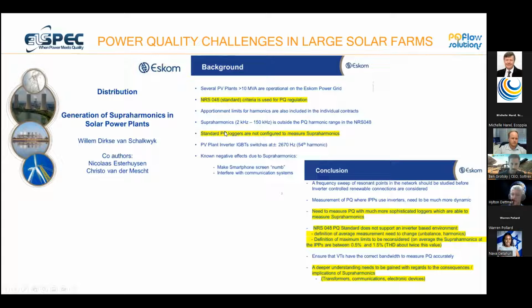He had standard NRS 048 type loggers in, but what they started looking at was a range of supraharmonics, which are outside of the standard 0 to 50 harmonic range that NRS 048 requires us to measure. So we are seeing that there's a higher harmonic range developing on the network in certain instances. It's not all over the place, but we need to be able to understand this, and we need to be able to understand what the implication is. Do we need to do something about it? And if so, how do we design and develop around this new market?